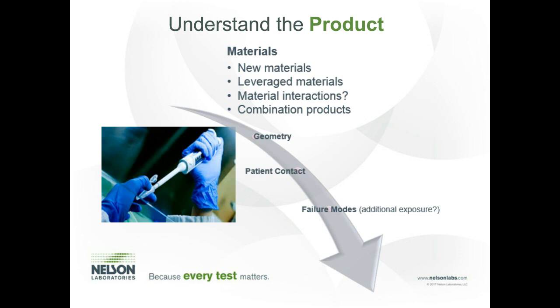If you're sourcing it from the same supplier, if it's going through the same processing, then that really helps leverage that risk. You still have to look at material interactions. There are some very unique synergies that can happen between materials that are not greatly understood in some cases, but I'll throw one out there that we do understand. It has to do with metals, more with cytotoxicity. There's quite a bit of metals, actually, that has cytotoxic potential. Silver, copper, zinc are some I just throw out there. And most of these have very similar types of toxicological endpoints on these cells. So if you have copper at a very low level, you may not have a response, but by adding another metal like zinc to the device, you may now have a response with a coupling of those two metals. So you do have to look at metal or material interactions.